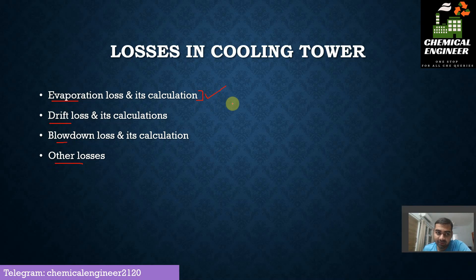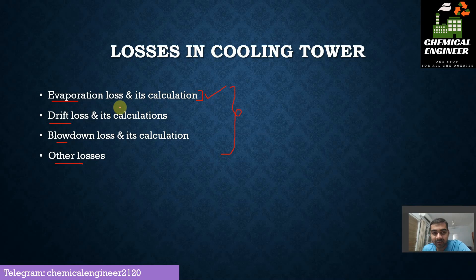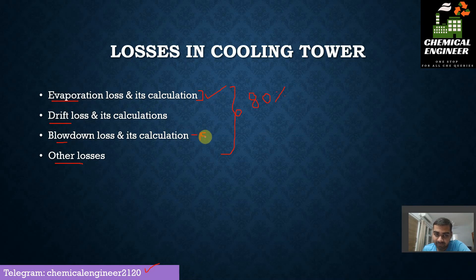In this video we are mainly focusing on evaporation losses in a cooling tower and how to calculate them. In a cooling tower, evaporation loss comprises about 80% of total loss. Other losses like blowdown account for around 15 to 20 percent, and the remaining percentage covers drift and other losses. This is how losses are divided in a cooling tower.